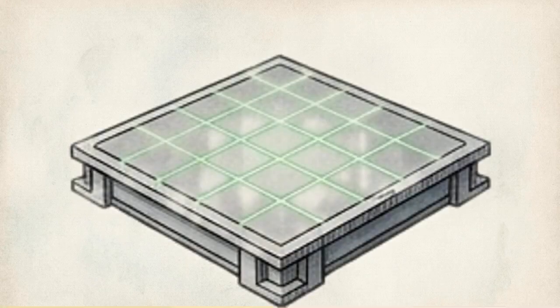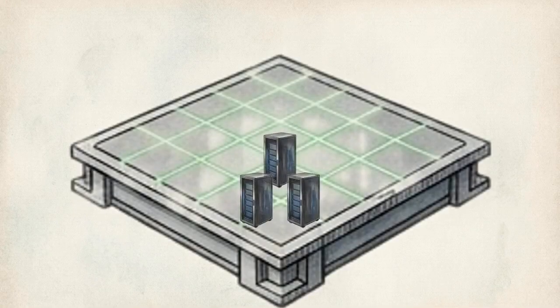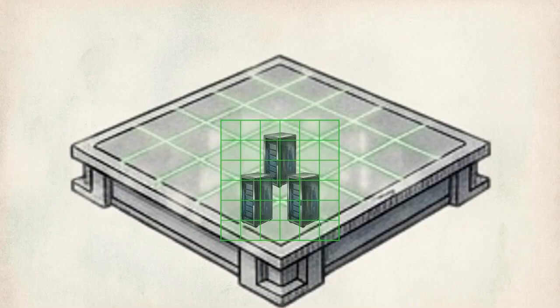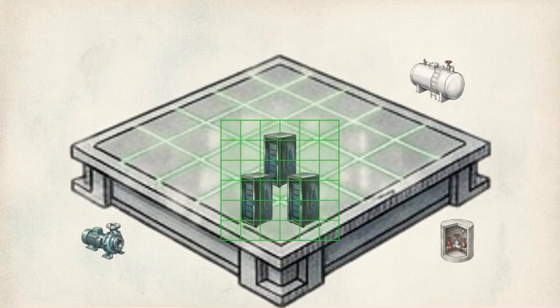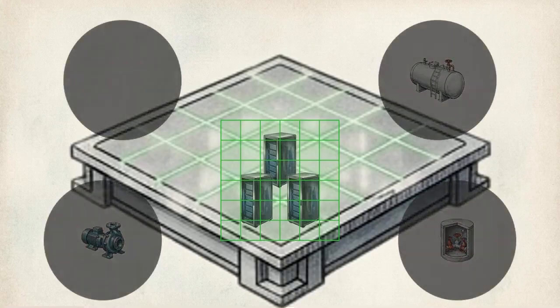Most traditional building management systems, or BMS, provide a reliable view of the core data hall. They map the main aisles and track ambient room conditions, but their visibility usually stops at the walls of the server room. This creates a telemetry blind spot. The facility relies on a network of peripheral assets: remote pumps, external water tanks, backup diesel supplies, and underground pipelines. Because they are difficult and expensive to wire, they are often left unmonitored.